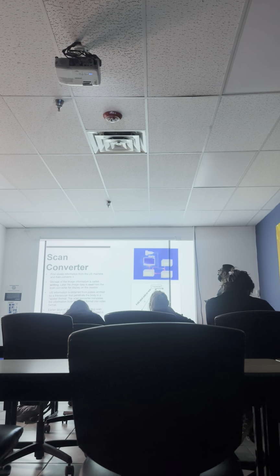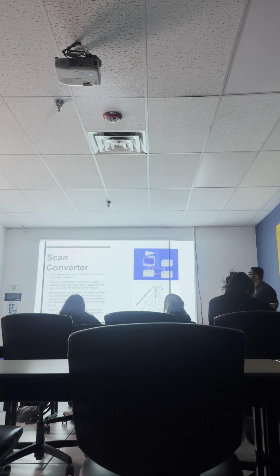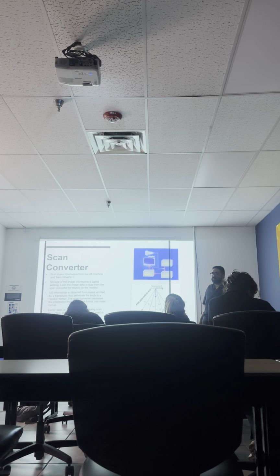So the scan converter translates the information from spoke format into video format. So from the format that looks like this into a video format where it makes an ultrasound image on the screen. In the earlier days of 2D imaging, we used analog scan converters.